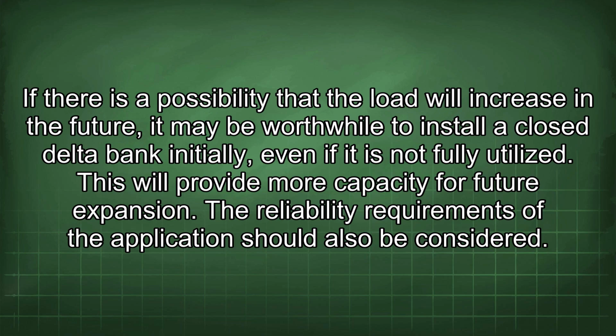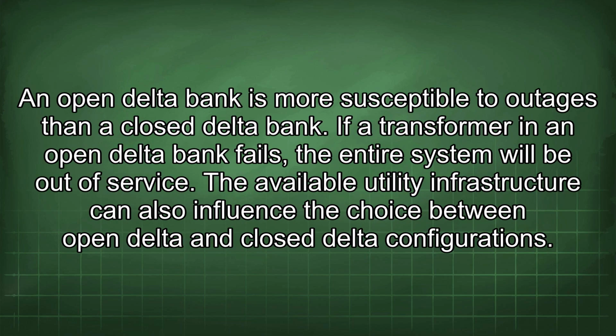The reliability requirements of the application should also be considered. An open delta bank is more susceptible to outages than a closed delta bank. If a transformer in an open delta bank fails, the entire system will be out of service.